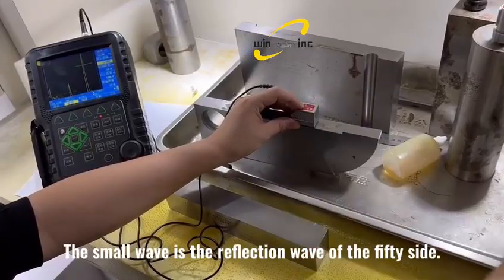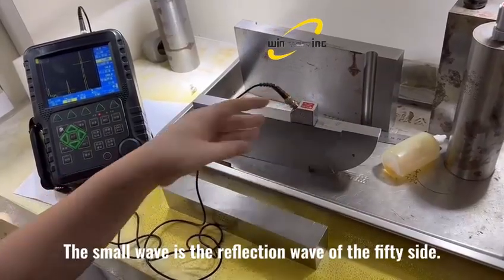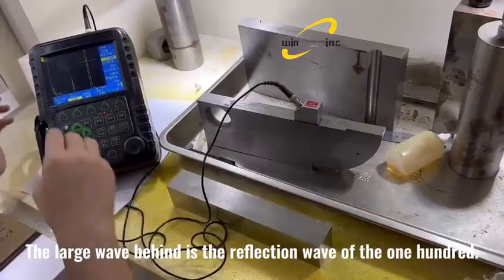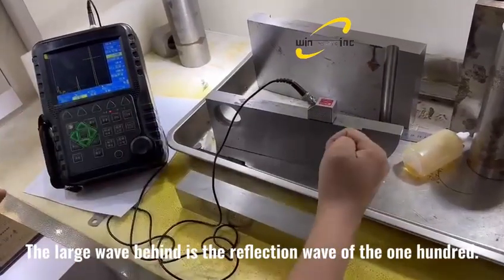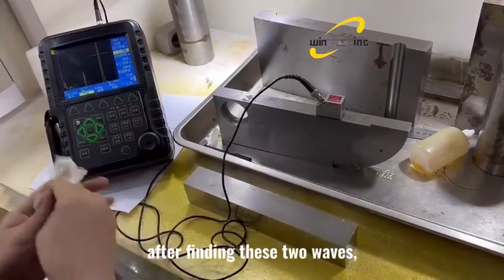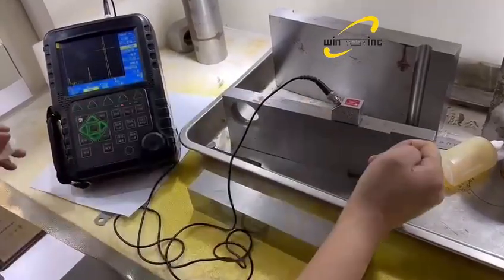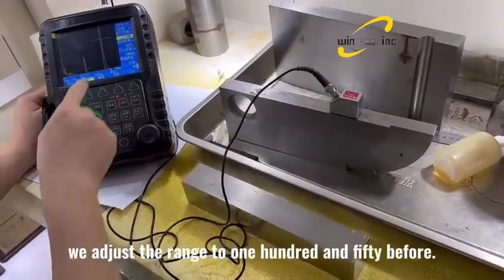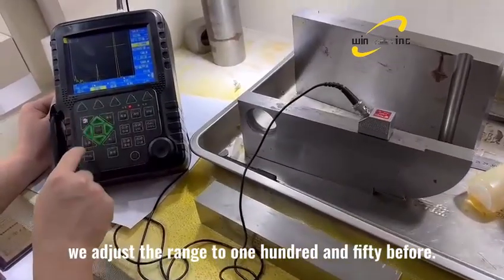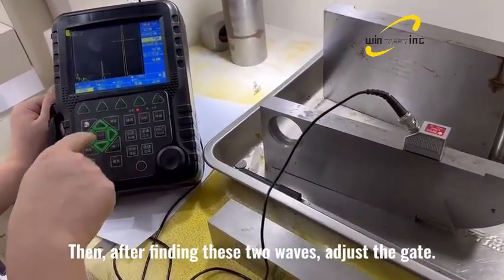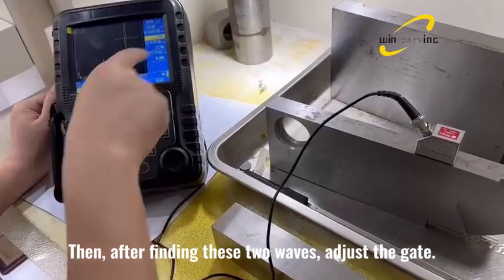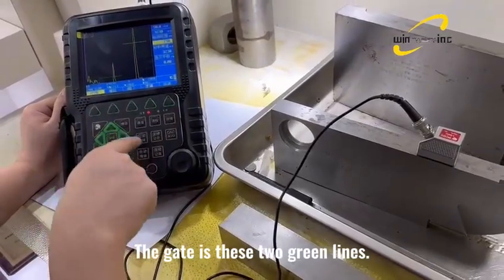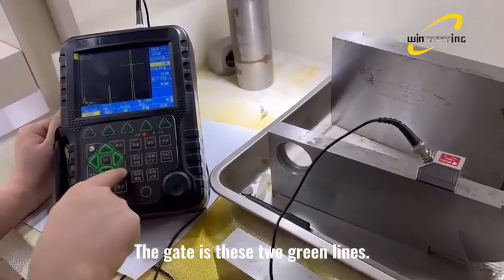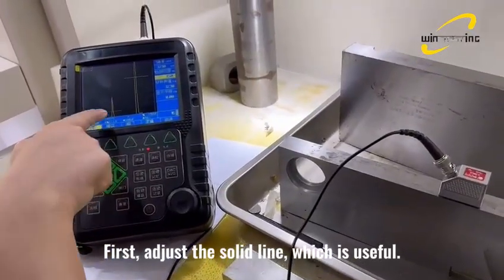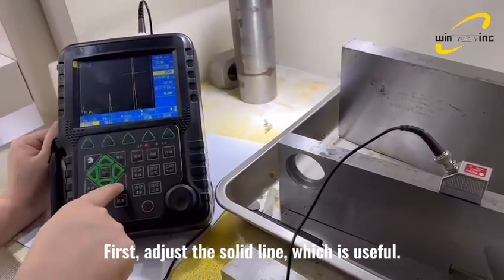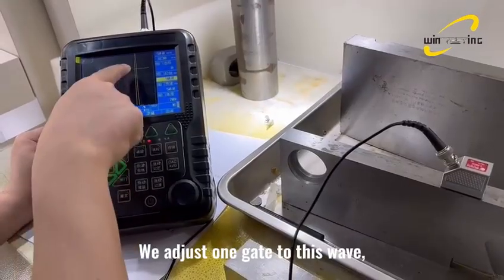The small wave is the reflection wave of the 50 side. The large wave behind is the reflection wave of the 100. After finding these two waves, normally we adjust the range to 150 before. Then, after finding these 2 waves, adjust the gate. The gate is these 2 green lines. First, adjust the solid line, which is useful. We adjust one gate to this wave.